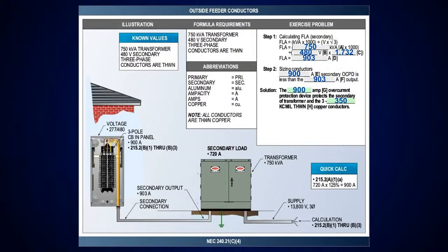But what we like to point out here is make sure you know the sizing of your overcurrent devices and how you do it on the application of 240.4(B) and 240.4(C). So once you see it's over 800 amps, you need to start looking at how high it's going up, because you need to drop down at that point.